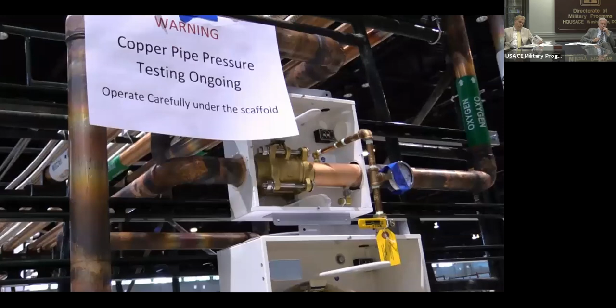On this project, we don't have the opportunity to use a building generator system, as it doesn't exist. So we had to put a 1,000 kW generator in to bring all the critical power for just the 750 pods. With that, we had to build this electrical room, which is all two-hour rated. You'll see in here the ATSs, the transfer switches, and step-down transformers for all the power that feeds the tents. Each one of the tents gets four critical feeds. We also have the tank farm and some medical equipment on that critical power, as well as the acute tents, which have additional outlets above and beyond the four in the standard tents.